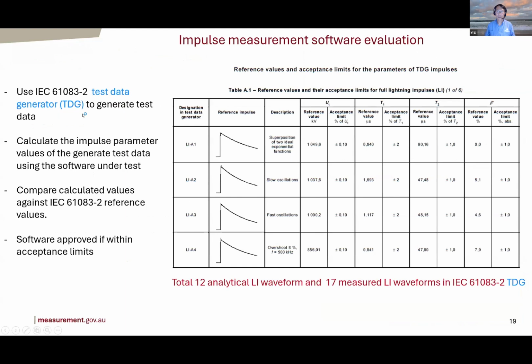So the software gives you an idea how that was performed. This IEC standard has a software package. It can generate software testing standards to suit your digitizer specification. And there are about 12 analytical waveforms with known reference values, and also 17 measured waveforms, also with known reference values. But these reference values are obtained by round robin intercomparison among many organizations, most of the NMIs.